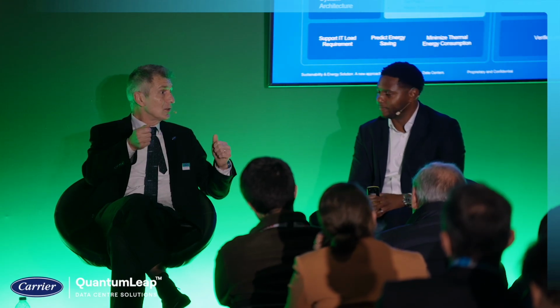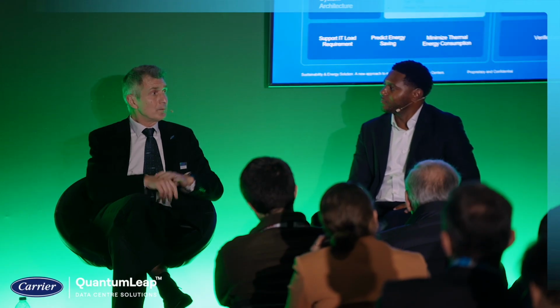And whether to force the system, by intelligent controls, to change the stage and go to the optimum state, or just propose to the operator, saying, if in this specific time you change your water flow, you may gain 5% of energy in the next 5 minutes. We're still working with data center operators on this, because I know how risk-averse people are, so we need to build a bit of confidence.